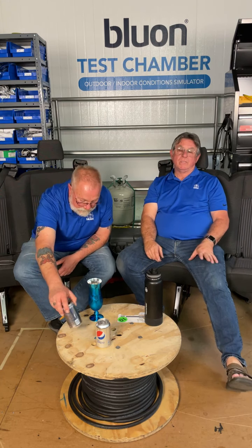Because if you think about the transformer, it's not a 120 plus 120 transformer, it's a 240 transformer. So you've got to have both sides of it there. So again, going back to basics, always check your voltage to make sure. I do some crazy things with electrical, but one of the things I always do is know if the equipment's hot. I know what's going on with it, and if I'm getting in there, I know there's power, or if I'm going to do other things, I make sure the power's off.